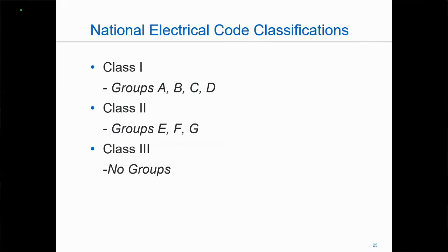And then we're going to want to know what is our group. So under Class 1, we have Groups A, B, C, and D, and this takes a closer look at the explosive properties of our gases and vapors. Groups E, F, and G under Class 2 take a look at what type of combustible dust I have in that particular area.